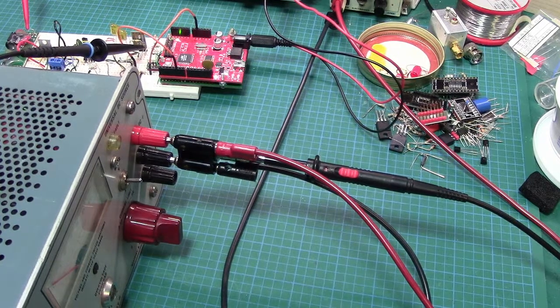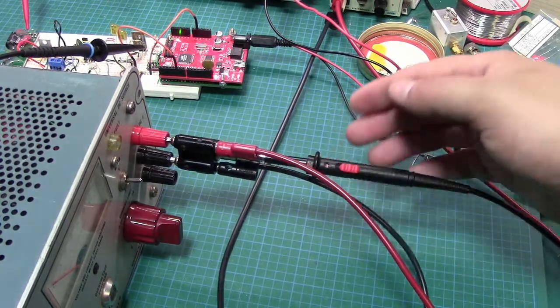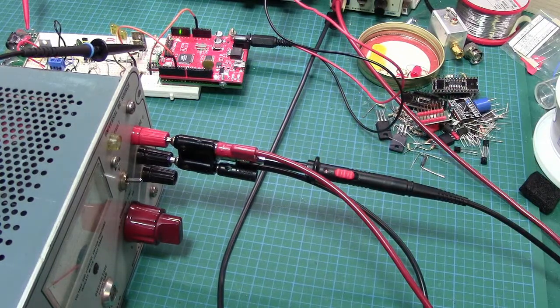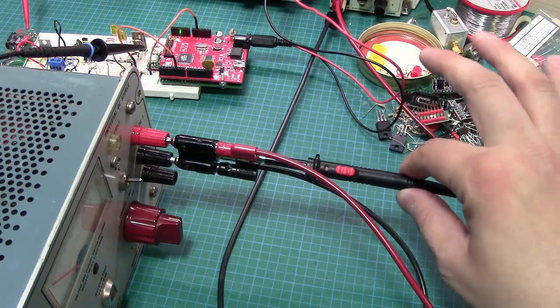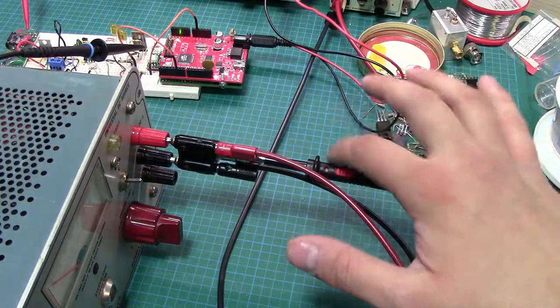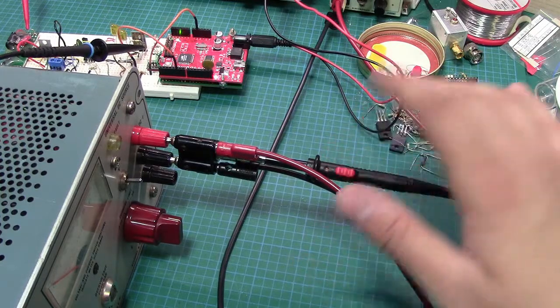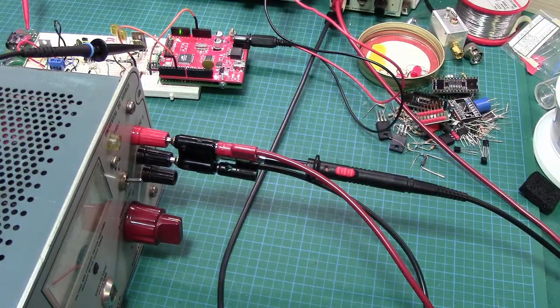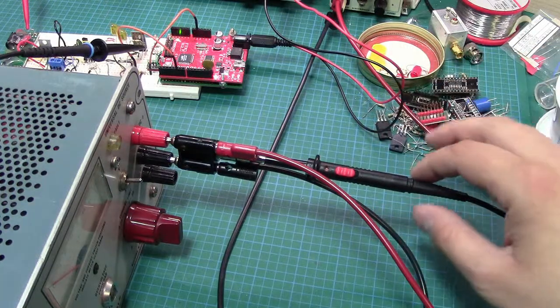So, that being said, we should be using the 1x setting, which will allow us to take a reading of a lower voltage with a bit better fidelity. But of course, the trade-off is that we can't get as high a bandwidth. In this case, this particular probe, if I remember correctly, is DC to 8 megahertz at its 1x setting, but that's okay because we're not looking for anything anywhere near that end of that range. So that's our first problem.